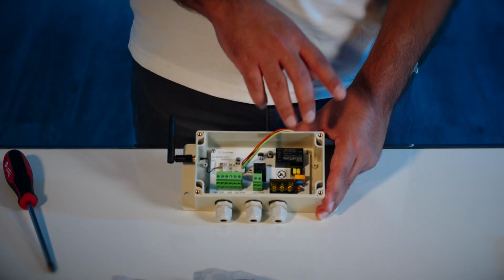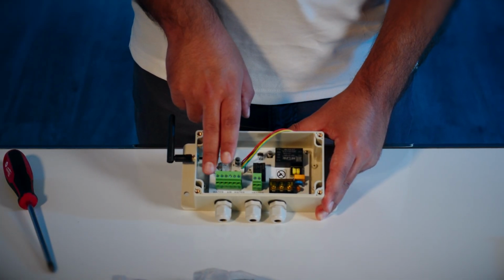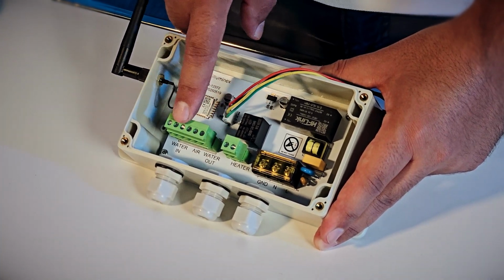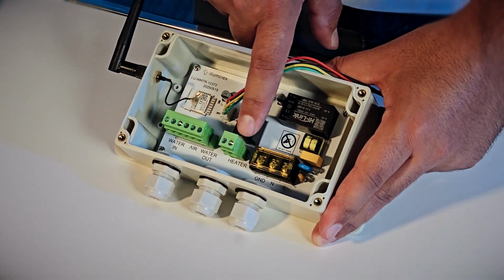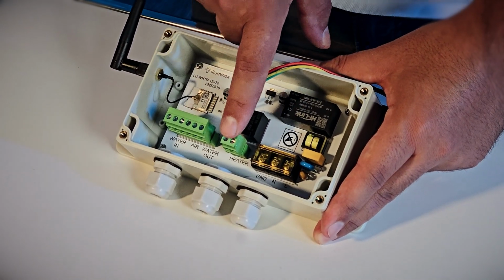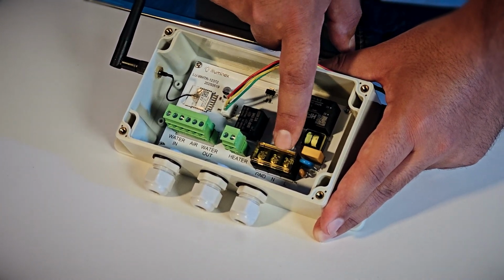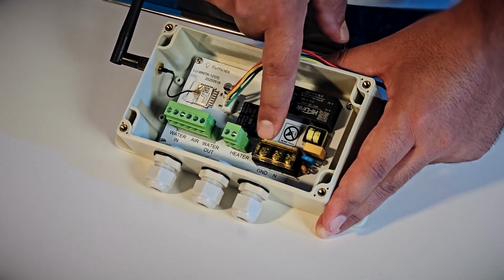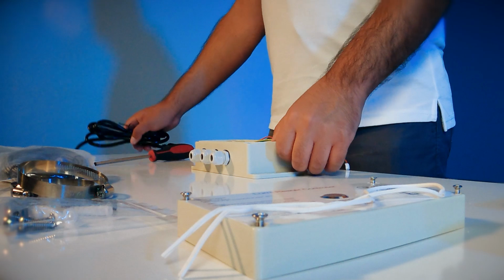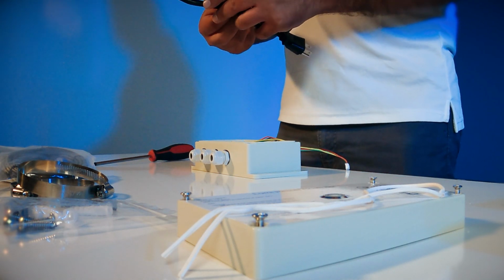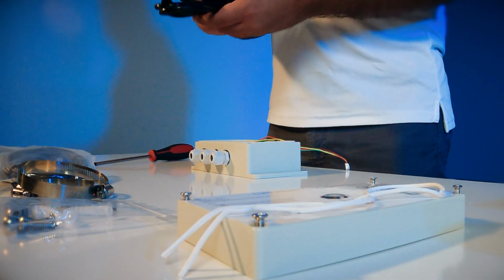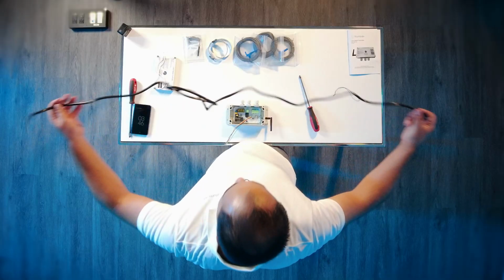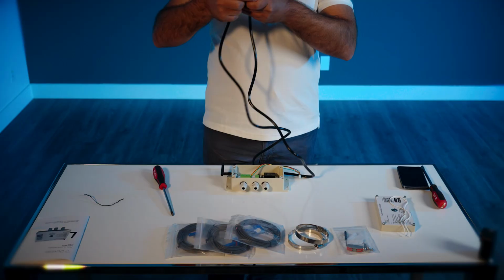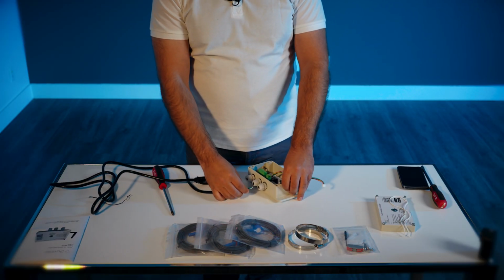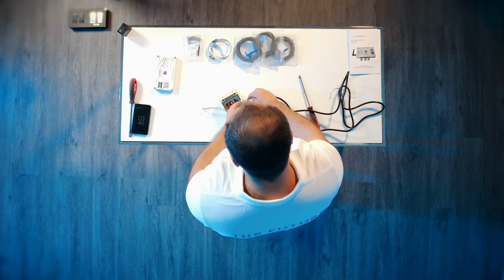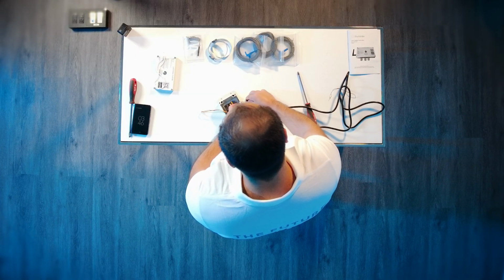All right, so once you open the heater controller, you can see inside we have 3 terminals. Firstly, we have the temperature sensor terminal. Then we have our dry contact wire terminal. And lastly, we have our high voltage input terminal. All right, so let's get started with our high voltage connection. So you take the supplied 6-foot long electrical cable and you can feed it into the very last dry liquid tight connector.